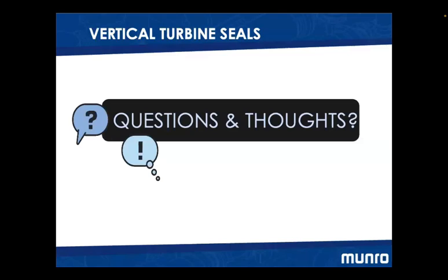Okay. So there is one question that just came in and says, how about the seals for a horizontal centrifugal pump? Do those need maintenance as well? So horizontal centrifugal pumps can be ordered and manufactured to utilize both mechanical and packing style seals. I would say the majority of irrigation application pumps are going to include mechanical style seals. And there is very little maintenance required to a mechanical style seal used in that application for horizontal centrifugal pumps, short of when there is a failure at a mechanical seal.